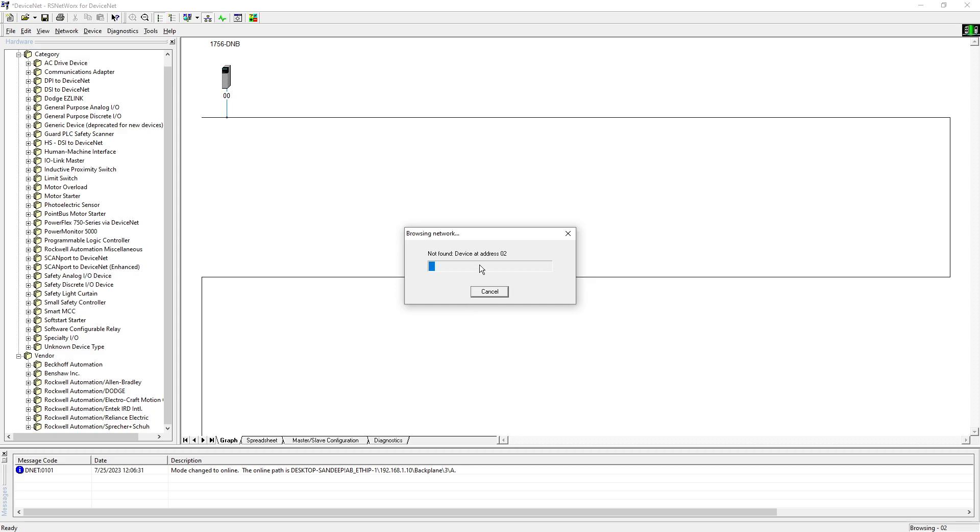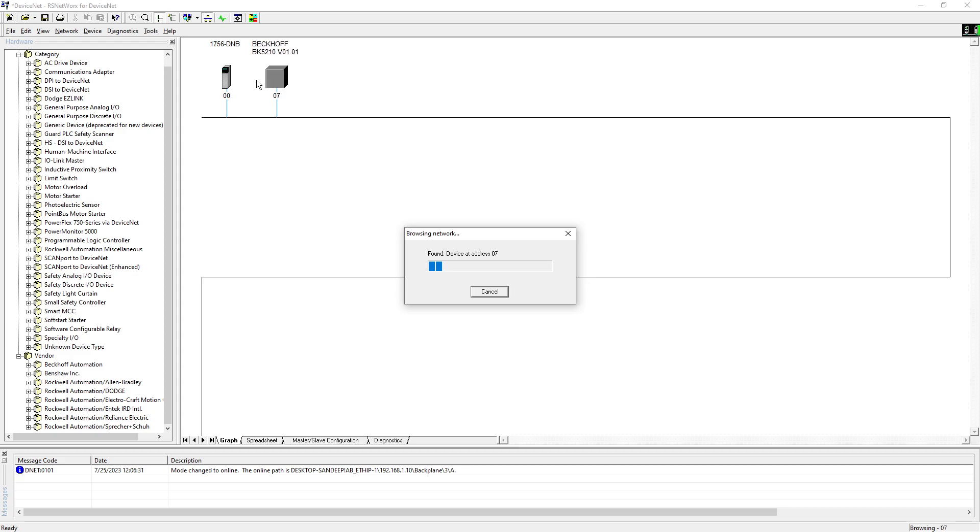It's gonna search nodes from zero all the way to 63. I put my device at device number seven, I believe. So it's gonna go to seven and you will be able to see the device over here. There you go, at seven I have found my Beckhoff module, so I can hit cancel over here.